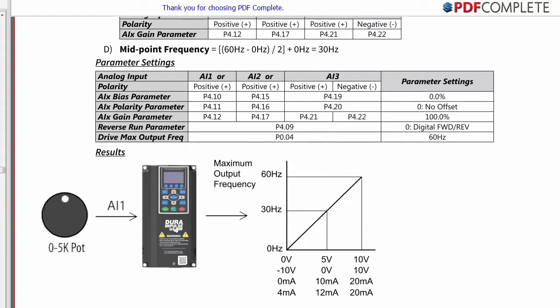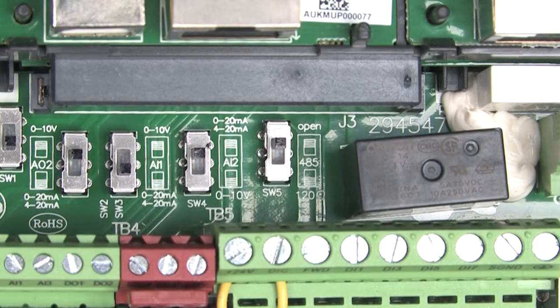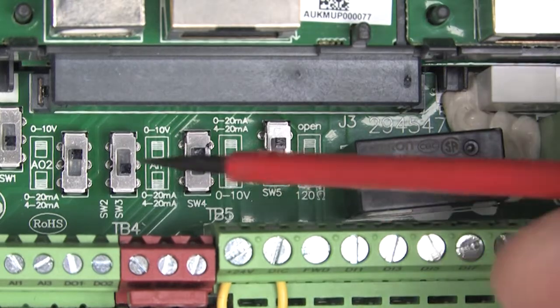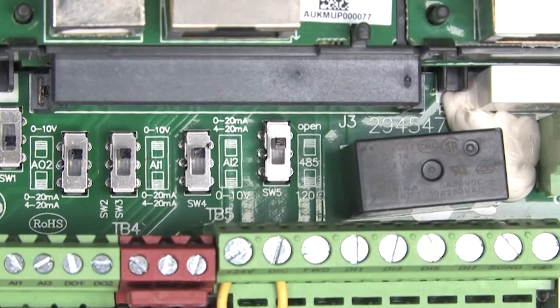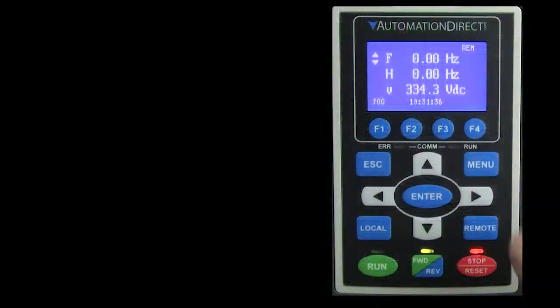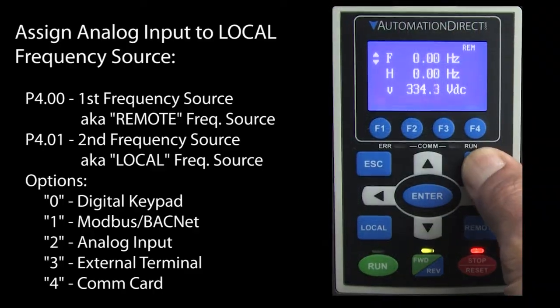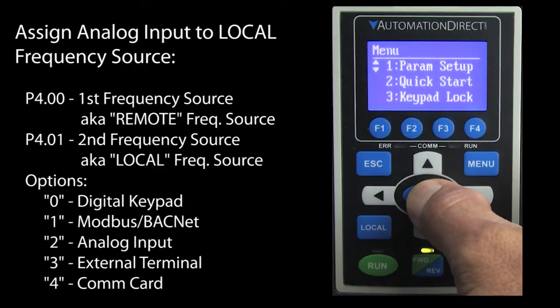Since the potentiometer is applying a voltage, we need to make sure the switch for analog input 1 is set to voltage. Now we need to tell the drive what we are doing.